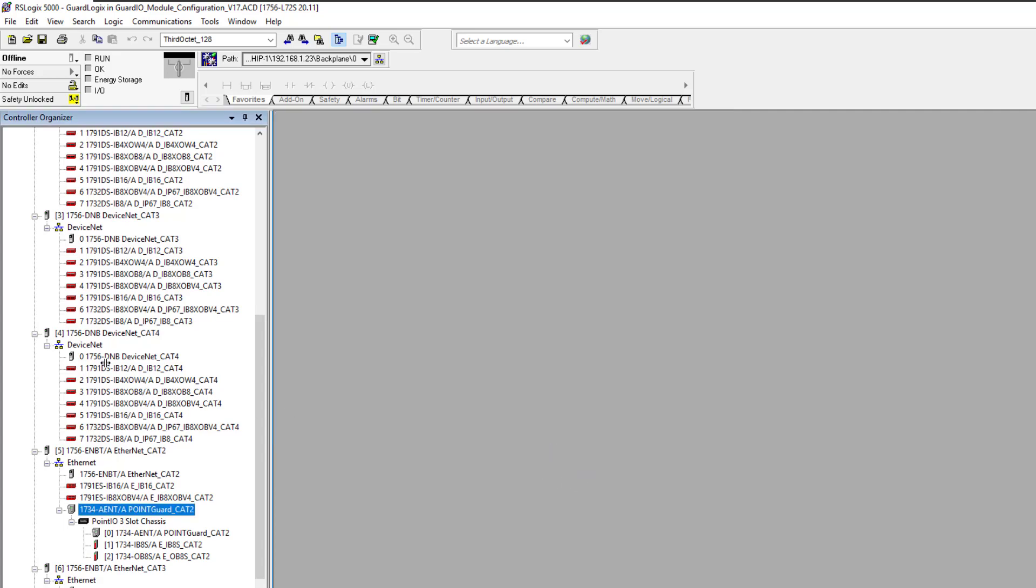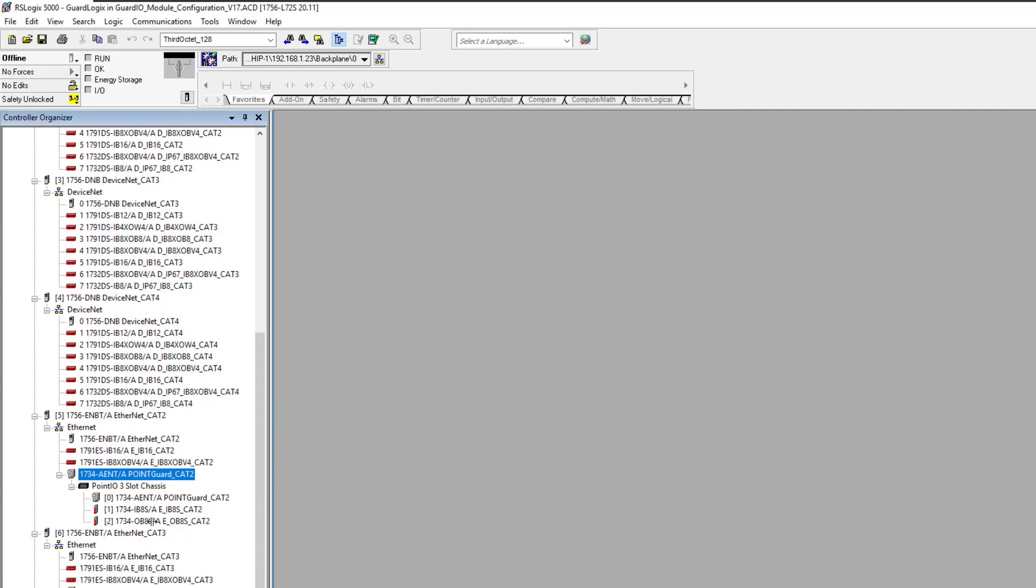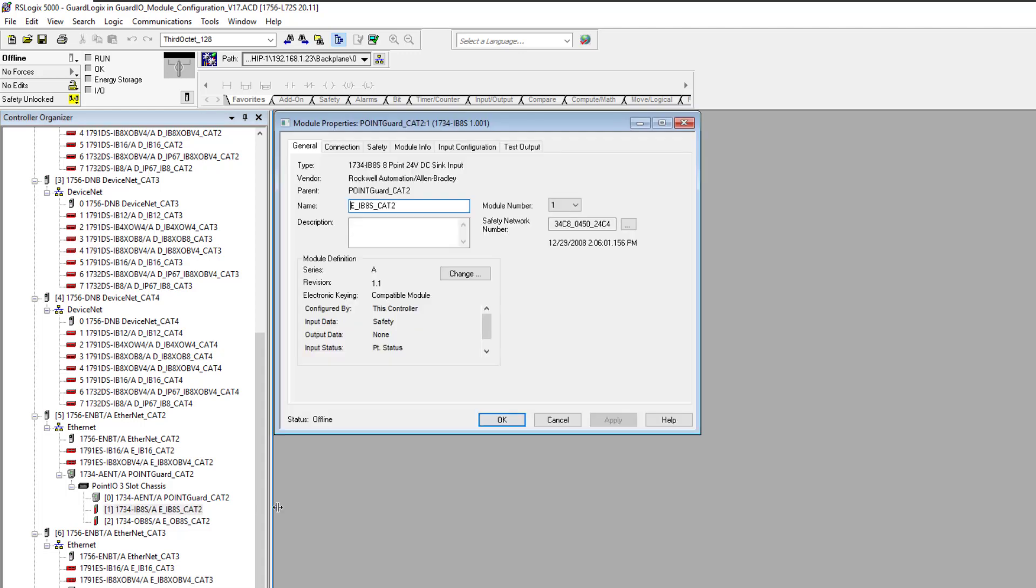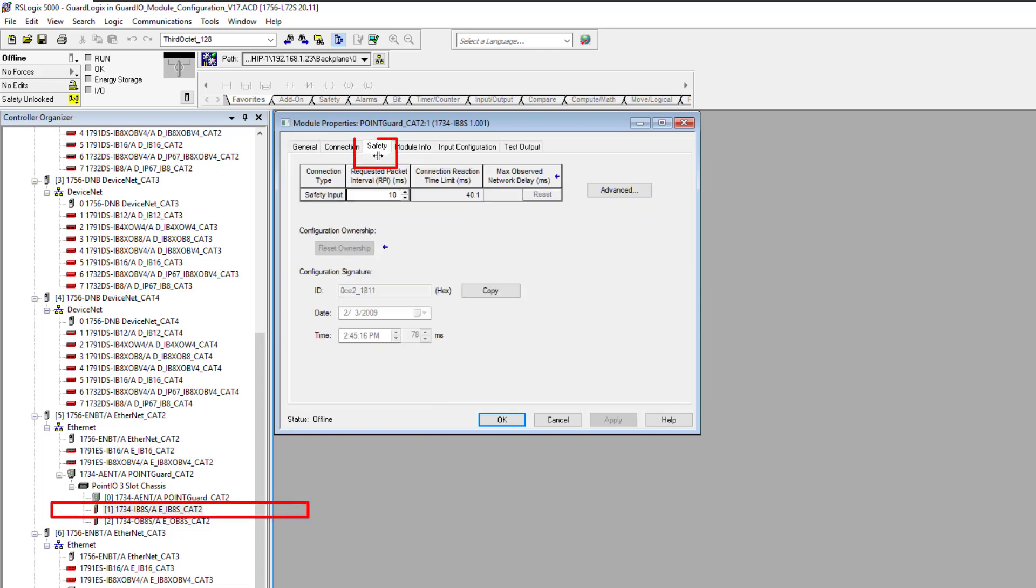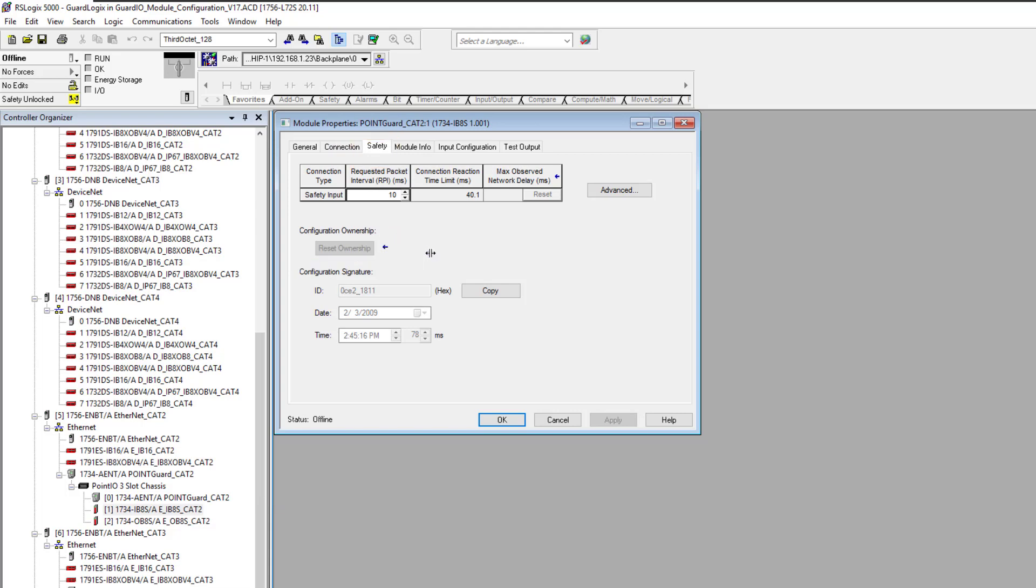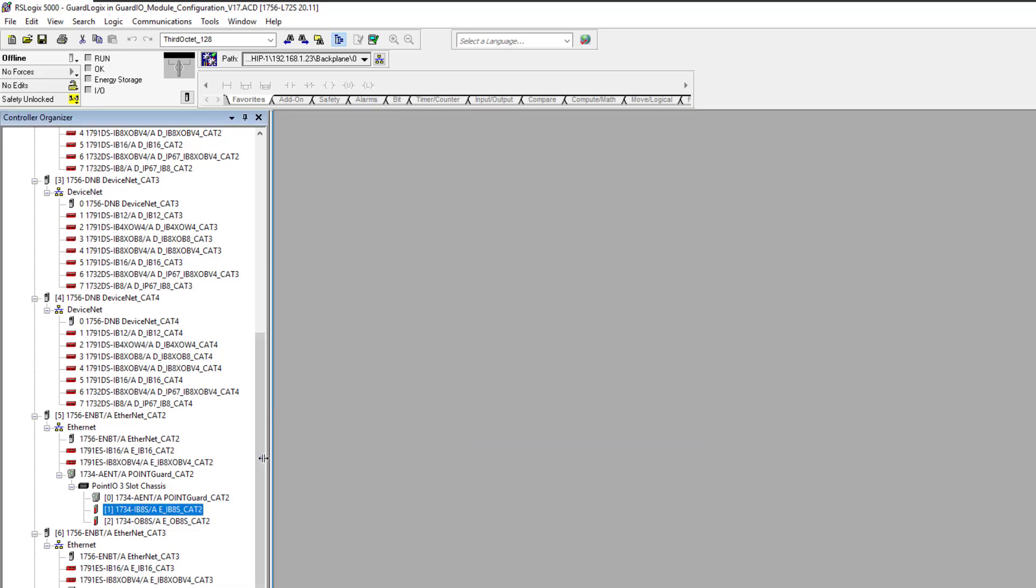However, in the instance of it being a safety device, like these are cards inside of it, if one of these cards went out, we would have to go into the safety tab right here and reassess the ownership of that card. And the reason that it does that, it gives it a timestamp, it gives it an ID, it gives it all the information, and then it basically gives it a signature and reestablishes communication to the actual processor. When it does that, everything will work properly.